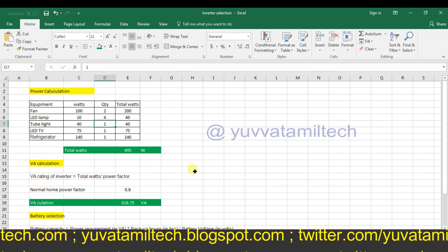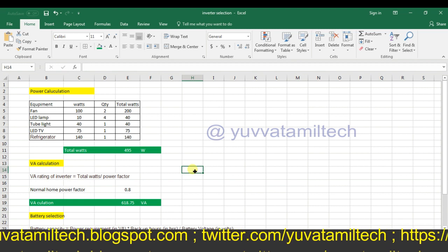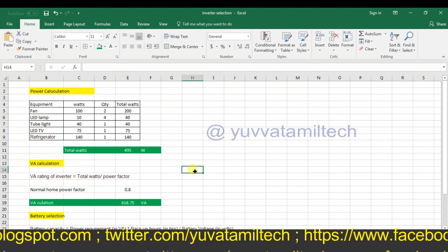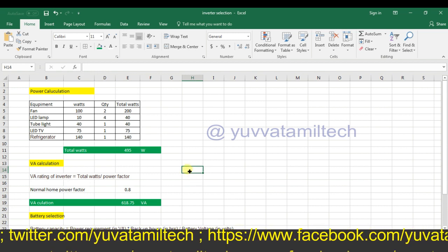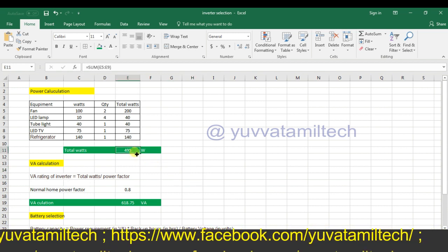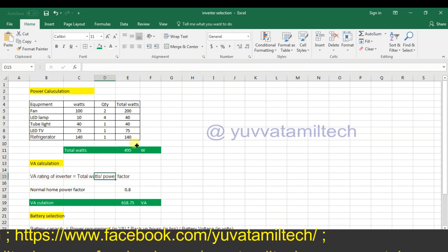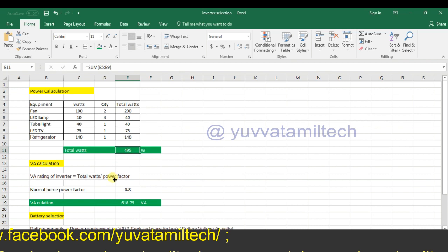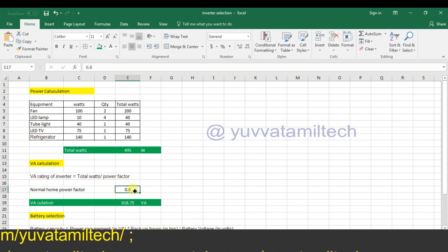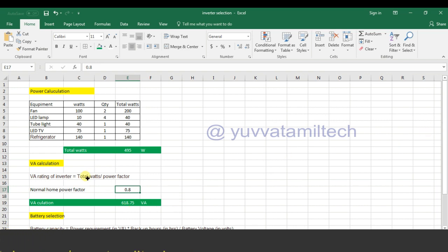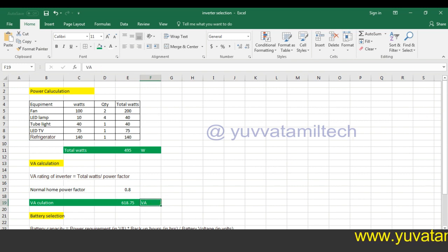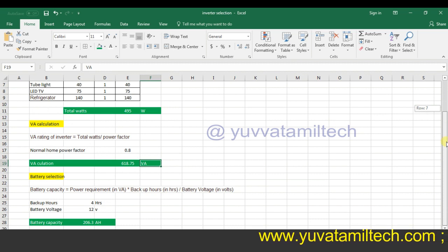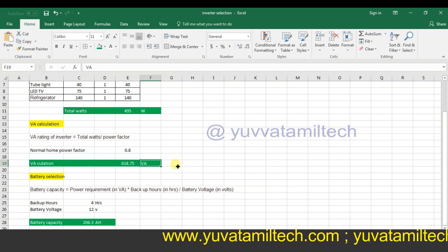For inverter selection, the rating is in Volt-Amperes (VA). The inverter selection is based on total load divided by power factor. The total load is 495W. The power factor is 0.8 by default. So VA calculation: 495 divided by 0.8 equals 618 VA. So 618 VA — the inverter selection is done.